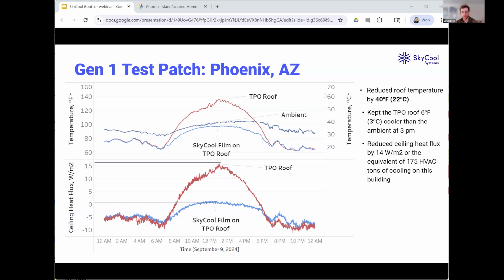The heat gain we're measuring, 15 watts per square meter, for a building of this size might translate to 200 tons of cooling capacity. By putting the film on this roof, a project we're hoping to do early next year, we can eliminate or prevent installing that much cooling capacity, reducing peak energy demand and energy use over the summer.